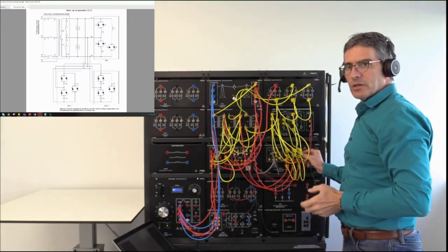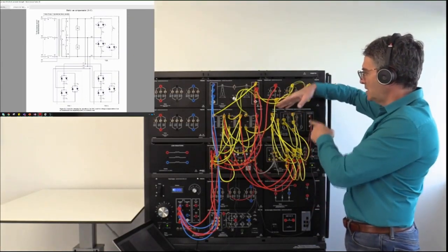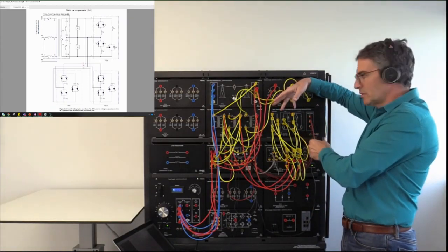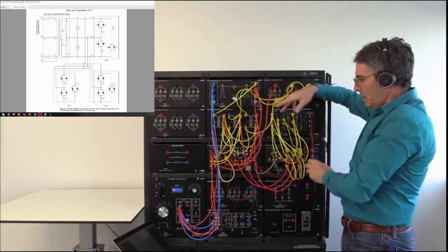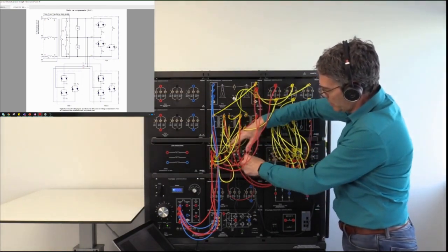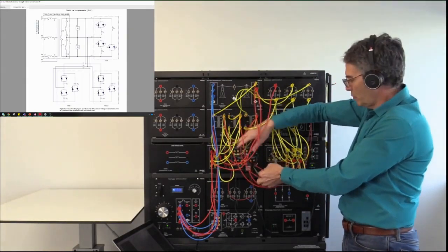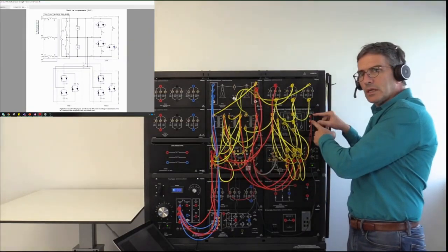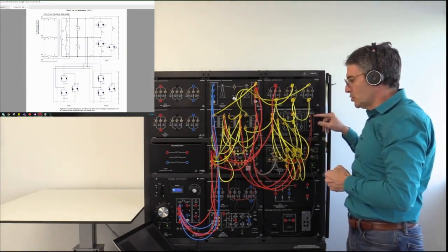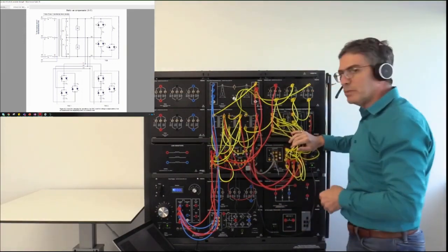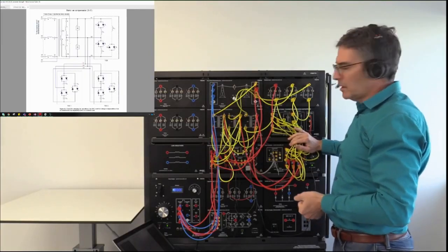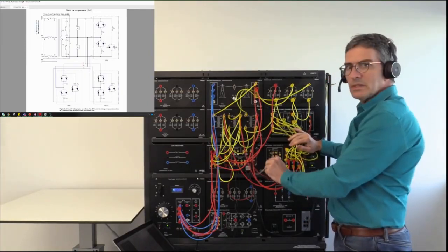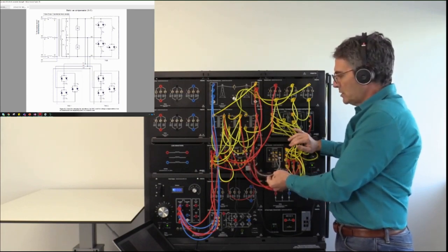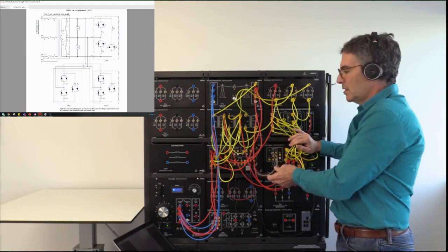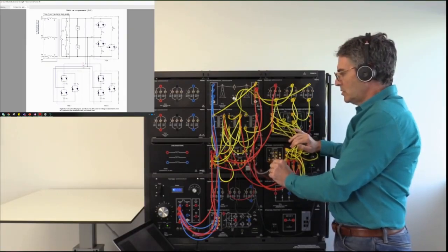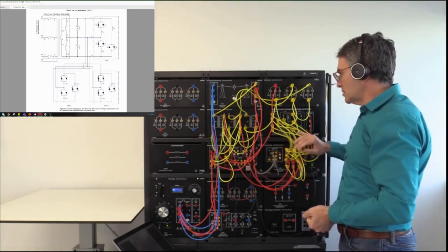Then we have a couple of control connections also required. We need to send a signal to the TSCs to turn them on or off, or insert them in the circuit or not. These control signals come from the data acquisition module. Digital outputs 1 and 2 of the data acquisition module are sent to TSC 1 and 2 inputs on our TSC module. Finally, the thyristors also need to be controlled, and they receive their triggering signal from the data acquisition module through the DB9 cable we already used last week when we presented our choppers and inverter circuits in the power electronics course. This same DB9 cable is used here to send the six triggering signals to our thyristors.